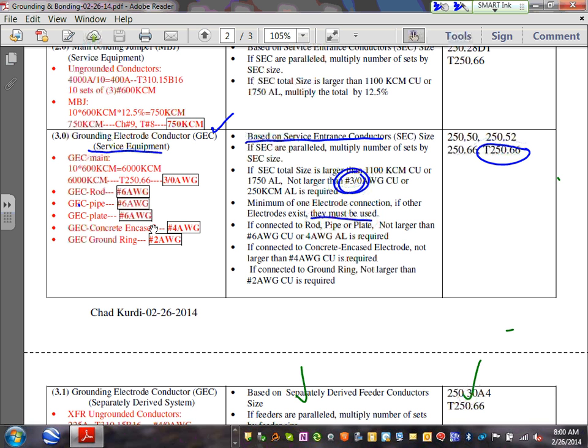If you're tying to a rod, a pipe, or a plate, you don't have to go larger than number 6 copper or 4 aluminum. Concrete encased electrode, you don't have to go larger than number 4. Ground ring, not larger than number 2. Any comments, guys? Any questions about grounding electrode conductor?